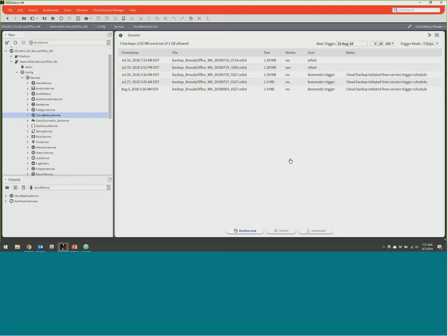What's the process or the practice for when you have multiple JACEs under a supervisor and you need to back everything up? That would be up to you. You could back up just the supervisor. Like if you have a provisioning set up where you're backing up to the supervisor already, you could just back up the supervisor and make sure that those backups for the JACEs are included. Yeah, the provisioning folders underneath the station for supervisor. Okay. So you just have to make sure in here, in conjunction with the cloud service.